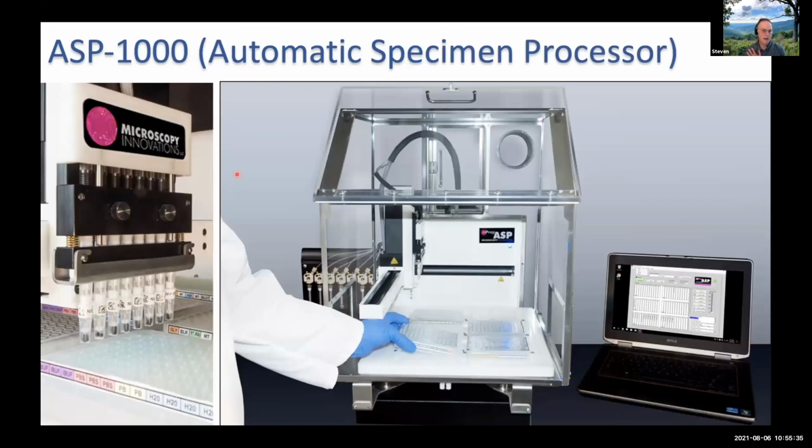So this is the pipetting head, and the specimen capsules are loaded onto the pipetting head. And there are 8 capsules for 8 specimens shown here. Grids mount the same way. I'll show that later. The reagents are loaded into microwell plates. Here, this one is labeled for the different reagents. And each capsule follows a different path through these well plates.